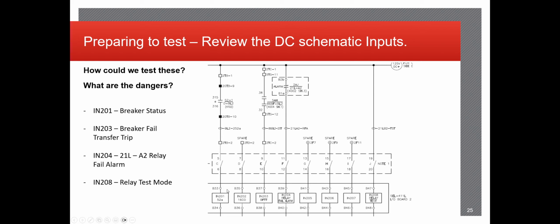In this case, with the breaker status, not a huge concern. Well, actually, if this breaker is in service, then there's no way to test this contact going up to the relay unless you take the breaker completely out of service, because the only way to operate this contact is to open and close the breaker. So as long as it's completely isolated, that's easy. You just operate the breaker once, you see this input go high when the breaker opens, and then close it back in. See that it goes away.